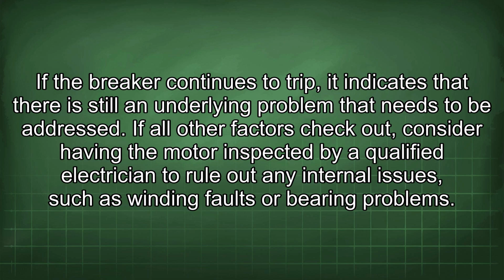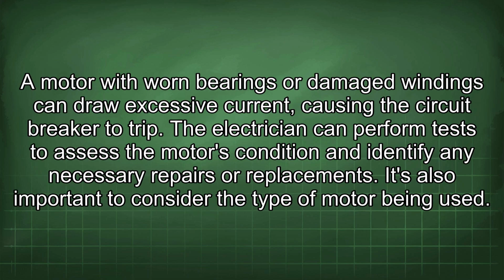If all other factors check out, consider having the motor inspected by a qualified electrician to rule out any internal issues, such as winding faults or bearing problems. A motor with worn bearings or damaged windings can draw excessive current, causing the circuit breaker to trip. The electrician can perform tests to assess the motor's condition and identify any necessary repairs or replacements.